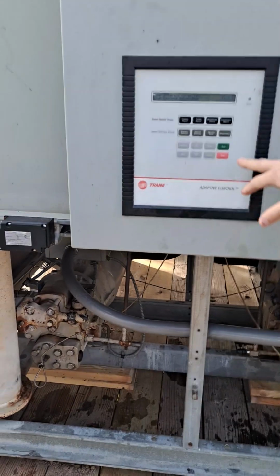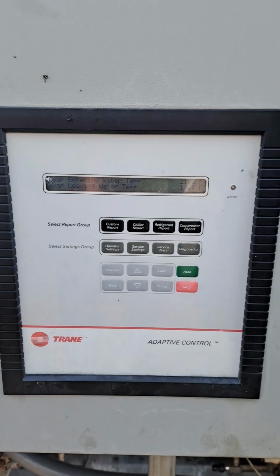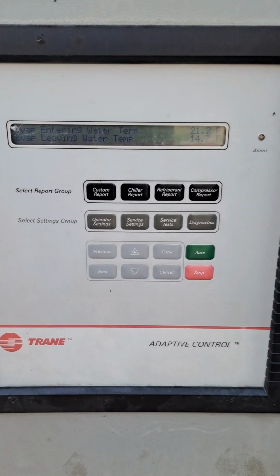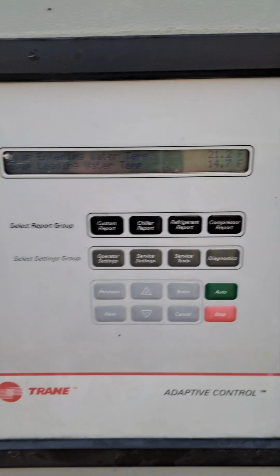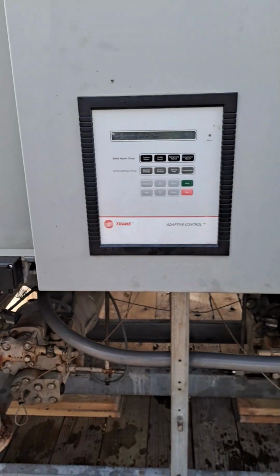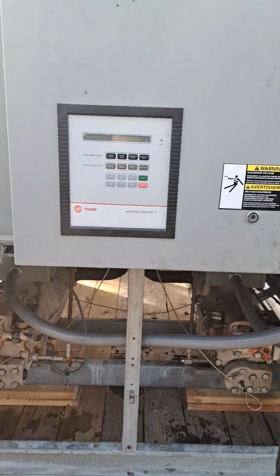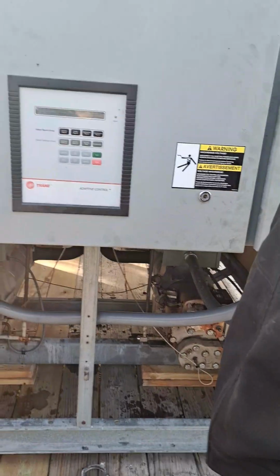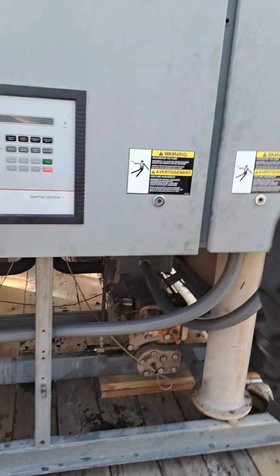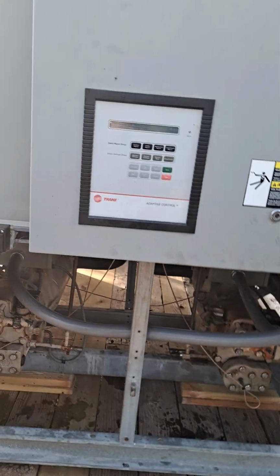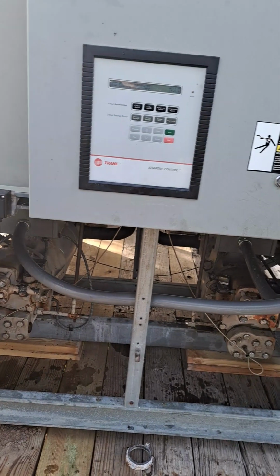To start it, all you gotta do is press auto. It'll go through a startup process. There's time delays in between starts, so they can be set for like 2 minutes. So when you start it back up, it'll take 2, 3, 4 minutes before it actually does start a compressor. Right. And then the compressors will start and stop depending on like hot temperatures.